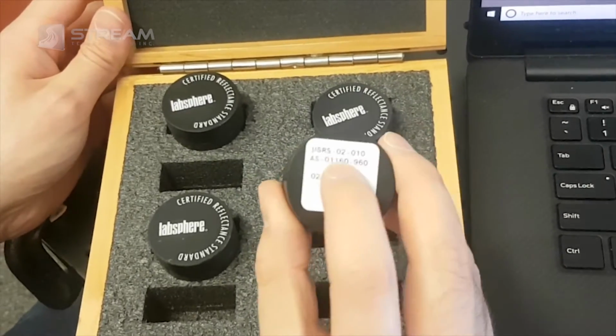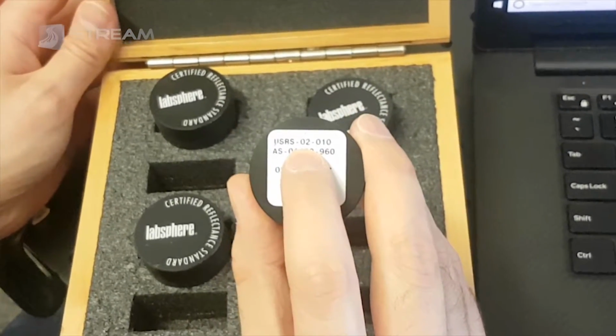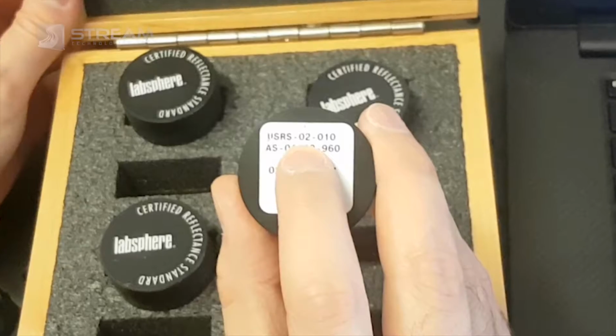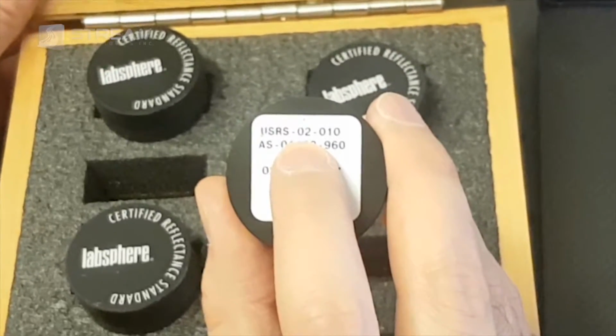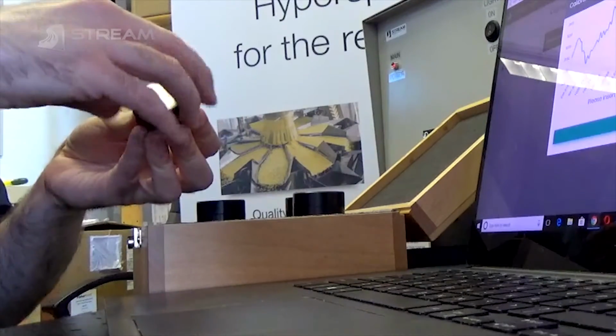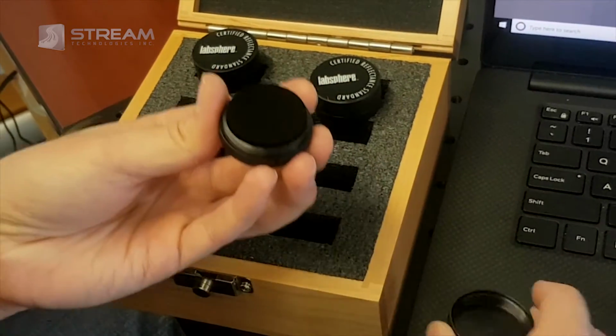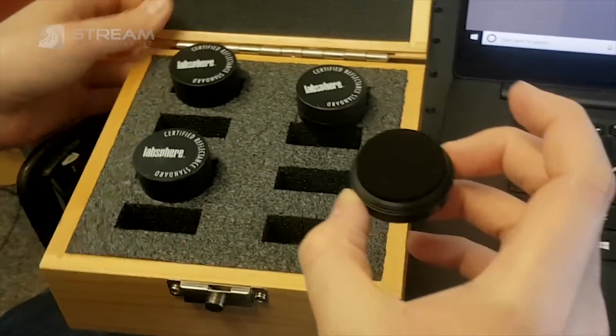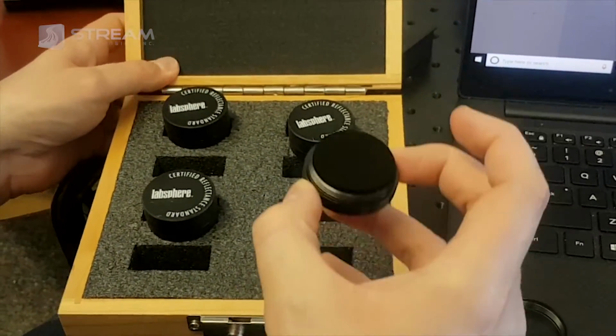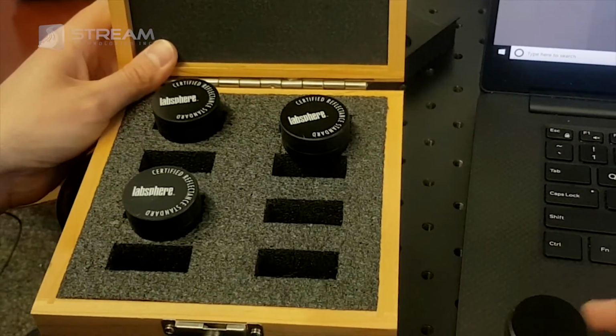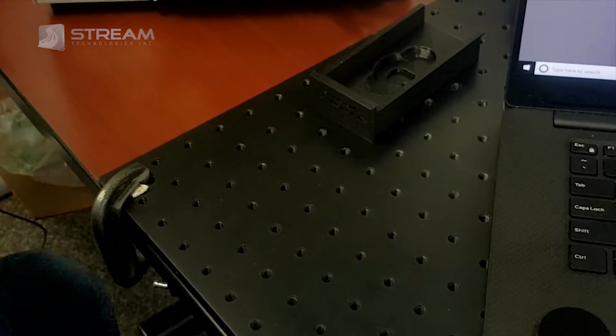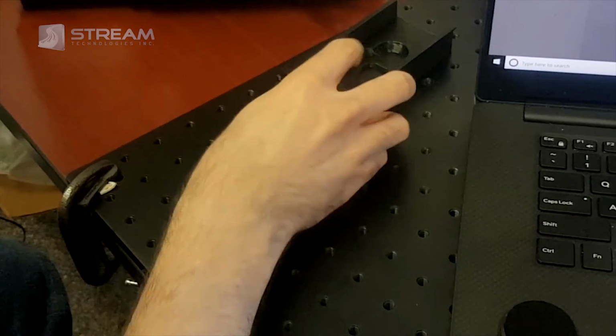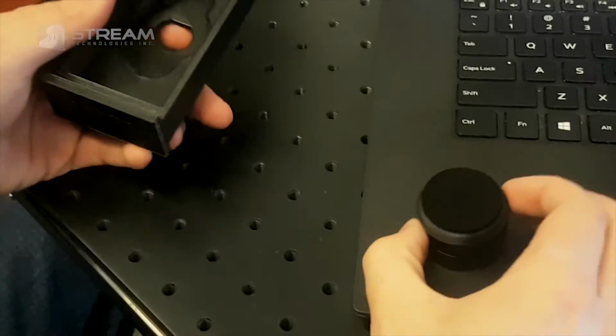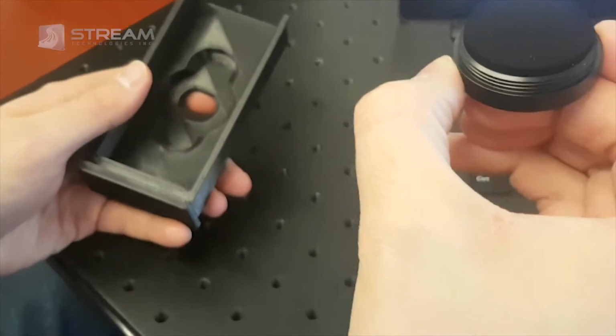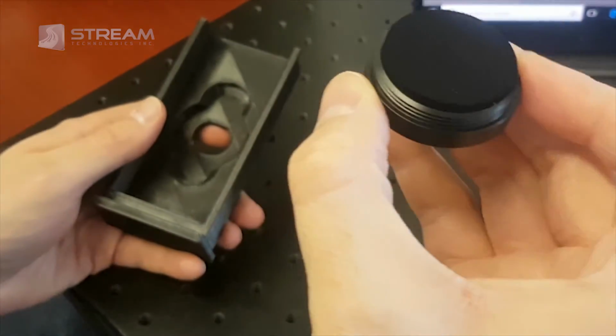If you just look on the back of them, they've got a number listed there that tells you what percentage reflectance they have. So I'll just open this up. They're a little screw on top, so just take them out like that. You can see this one's a 2%, so that means it only reflects about 2% of the light back. Make sure with these reflectance standards that you don't touch the reflective surface. This is because once they start getting dirty, they'll basically change their reflectance values.